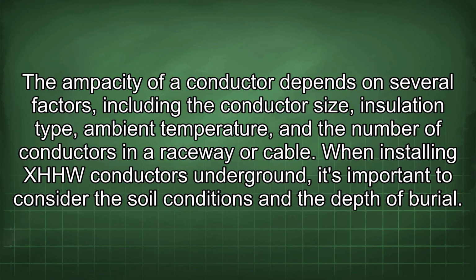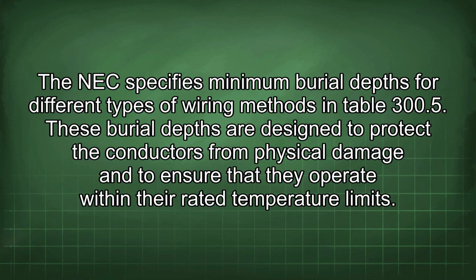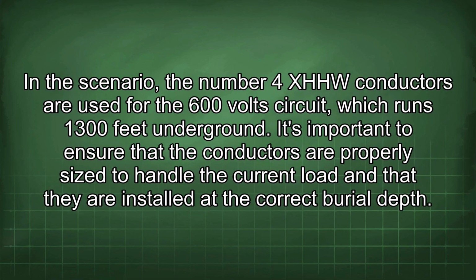When installing XHHW conductors underground, it's important to consider the soil conditions and the depth of burial. The NEC specifies minimum burial depths for different types of wiring methods in Table 300.5. These burial depths are designed to protect the conductors from physical damage and to ensure that they operate within their rated temperature limits. In this scenario, the number 4 XHHW conductors are used for the 600-volt circuit, which runs 1300 feet underground. It's important to ensure that the conductors are properly sized to handle the current load and that they are installed at the correct burial depth.